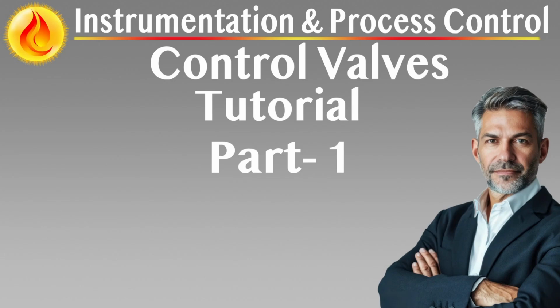Types of control valves and their application. Rotary valve preference and application guidance. In process applications permitting their use, rotary valves are generally favored over linear motion valves due to superior robustness, higher capacity, better turndown ratios, and reduced fugitive emissions.